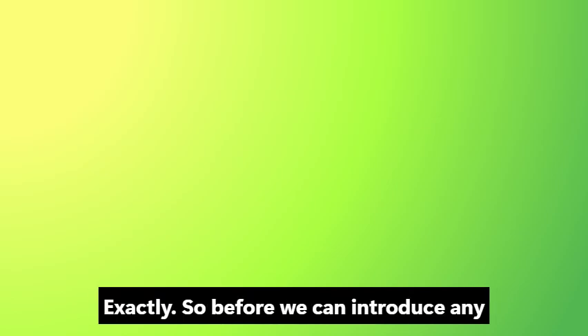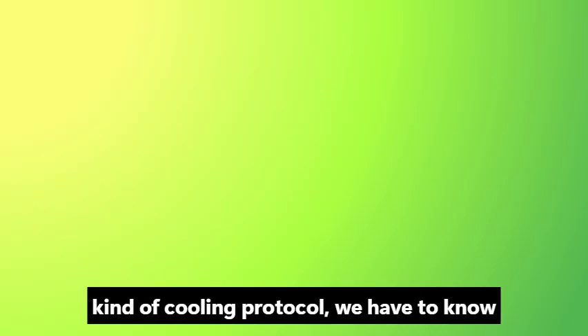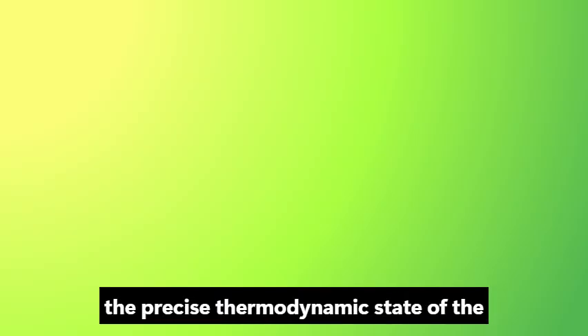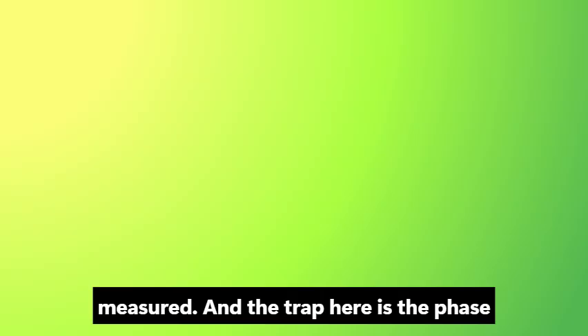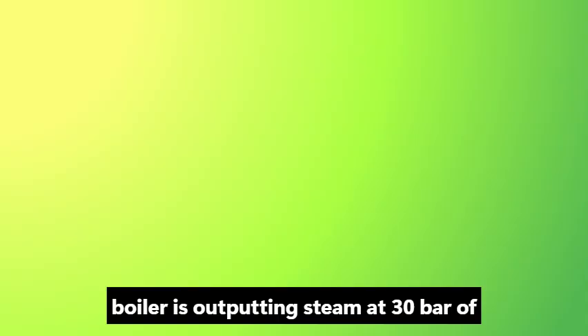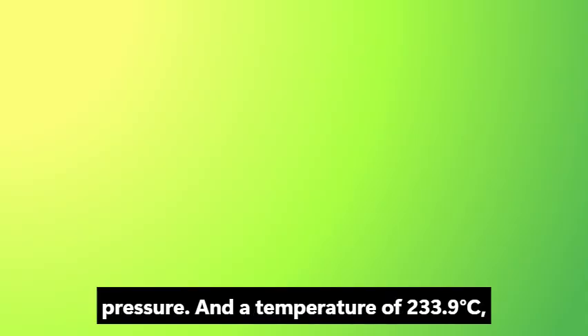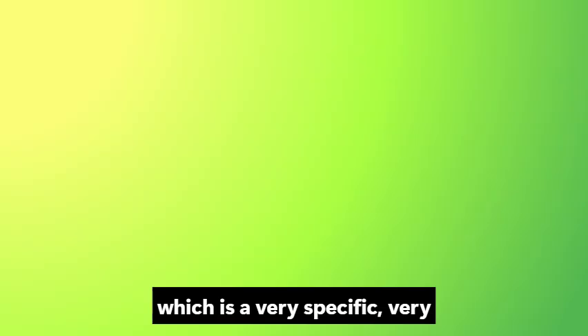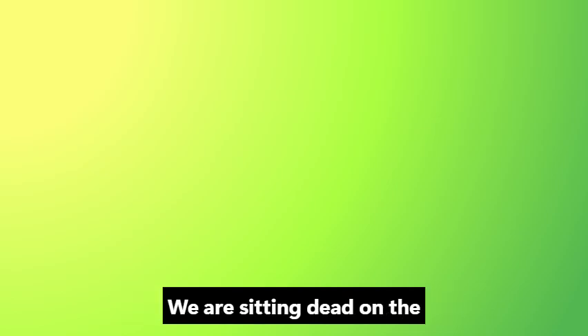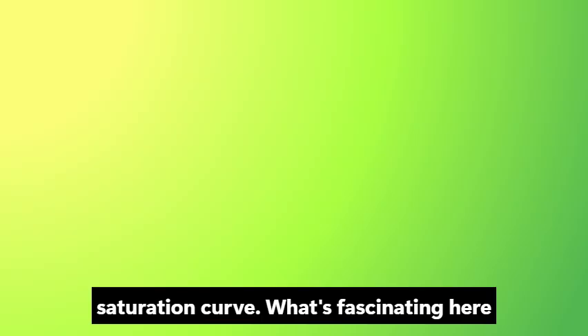Exactly. Before we can introduce any kind of cooling protocol, we have to know the precise thermodynamic state of the steam flowing through that main header. You can't fix what you haven't measured. And the trap here is the phase boundary. According to the notes, the boiler is outputting steam at 30 bar of pressure and a temperature of 233.9 degrees Celsius. A very specific, very problematic number. Because at 30 bar, water boils at exactly 233.9 degrees. We are sitting dead on the saturation curve.